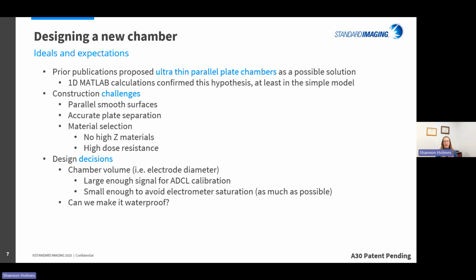So design decisions about the chamber: how big are we making it, the chamber volume, if we're talking about a parallel plate chamber where we're kind of fixed at our target of 0.3-ish millimeter separation. We control the chamber volume by changing the electrode diameter. We'd like to have something that gives us a large enough signal that it can be calibrated at one of the accredited dosimetry calibration labs, but small enough that we're not saturating all of the electrometers that are on the market, particularly ours, of course. But it's not saturating the electrometers when we're doing these flash irradiations and flash measurements. And then, of course, you want to put it in water. Can we make it waterproof and still make it something that is just as repeatable to construct and just as robust to dose?